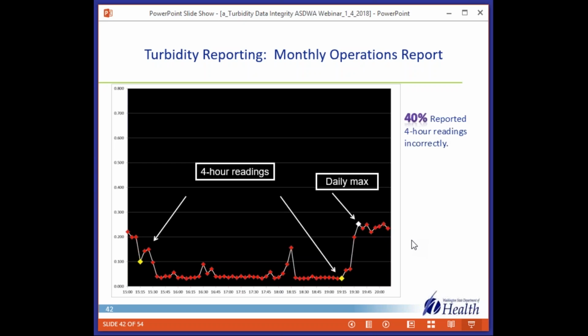We found that 40% of water systems were reporting the 4-hour readings incorrectly. Some set a set point. They would set their turbidimeters to trigger that first reading when you hit 0.2. So some of these might actually be an hour or more after filter startup instead of the first 15 minutes. 44% of the systems were not reporting the required absolute maximum for the day. The most common mistake here was to report the highest of the 4-hour readings. One water system was using the average of the 4-hour readings as the maximum for the day.